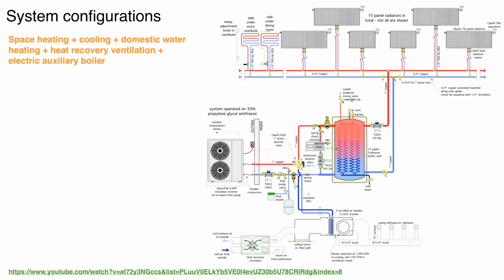Here's a system. This is actually one we talked about in Coffee with Caleffi back, I believe it was in February. This is a system that brings together 10 panel radiators, 2 zones of floor heating, and these are all relatively small room by room zones, variable speed circulator, reverse indirect, electric boiler backup. Here's our monoblock heat pump, and then our diverting valve that goes out to our cooling coil.